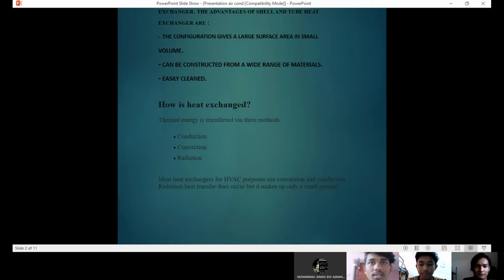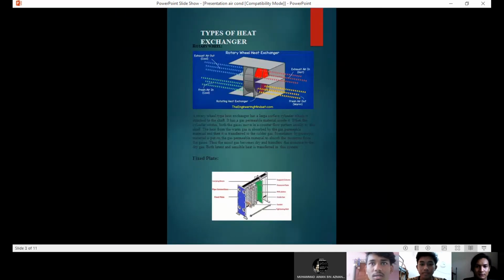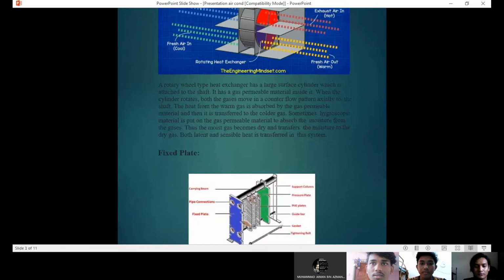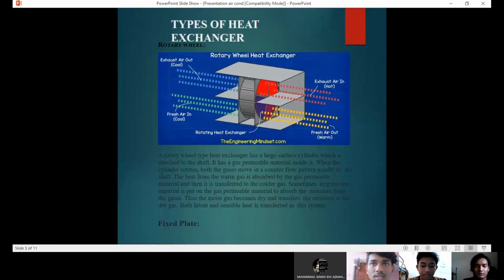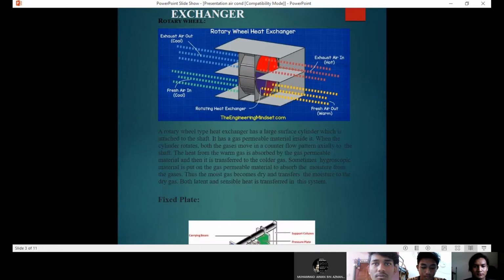There are many types of heat exchanger. Firstly, the rotary wheel. A rotary wheel type of heat exchanger has a large surface cylinder which is attached to a shaft. It has gas permeable material inside. When the cylinder rotates, both the gases move in a counterflow pattern, axially to the shaft. The heat of the warm gas is absorbed by the gas permeable material, then it is transferred to the cooler gas. Sometimes a hygroscopic material is put on the gas permeable material to absorb the moisture from the gases.